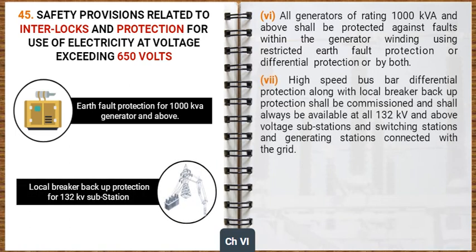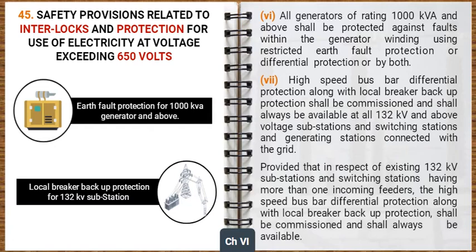High-speed bus bar differential protection along with local breaker backup protection shall be commissioned and shall always be available at all 132 kilovolt and above voltage substations and switching stations and generating stations connected with the grid, provided that in respect of existing 132 kilovolt substations and switching stations having more than one incoming feeders, the high-speed bus bar differential protection along with local breaker backup protection shall be commissioned and shall always be available.